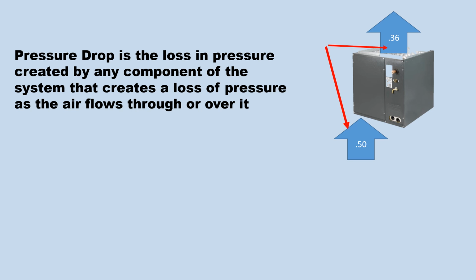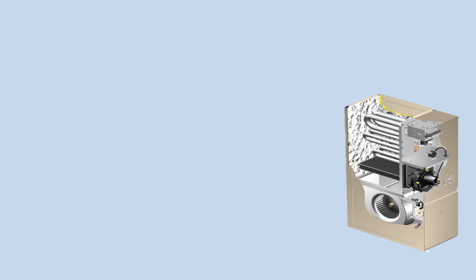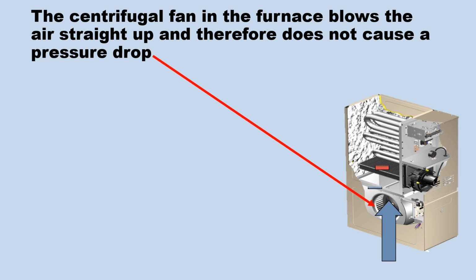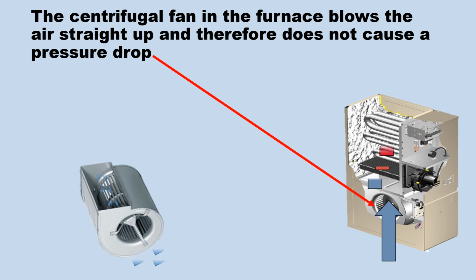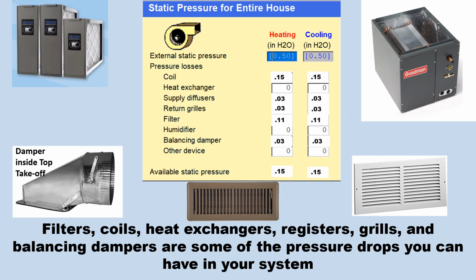Pressure drop is the loss in pressure created by any component of the system that creates a loss of pressure as the air flows through or over it. The centrifugal fan in the furnace blows the air straight up and therefore does not cause a pressure drop. Filters, coils, heat exchangers, registers, grills, and balancing dampers are some of the pressure drops you can have in your system.